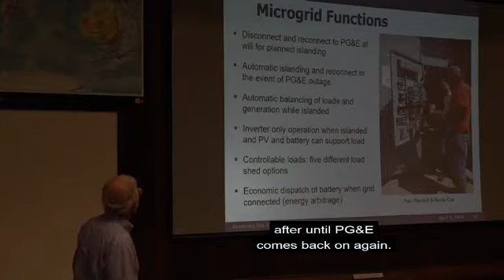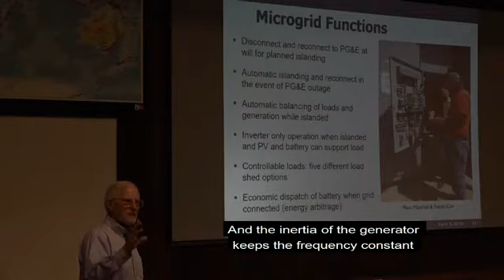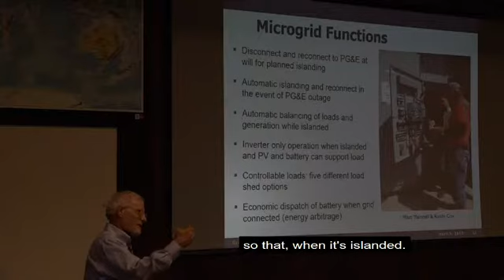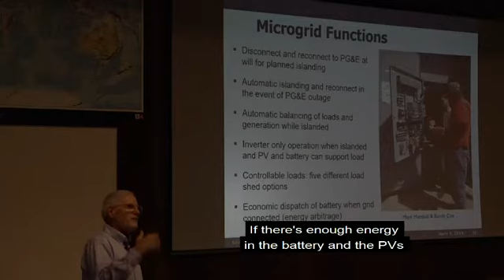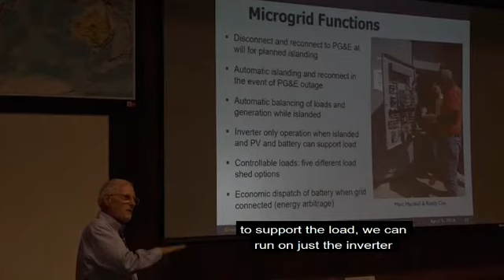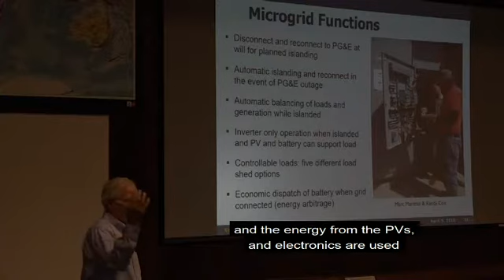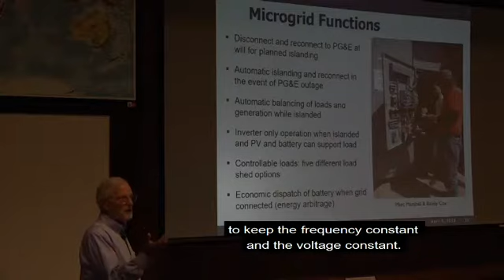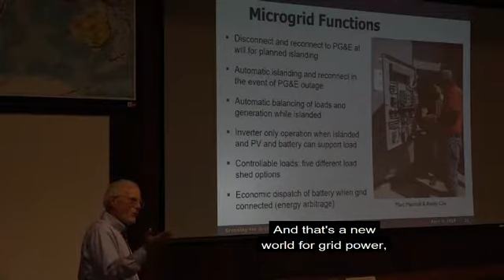The interesting thing is, most of our power systems rely on rotating generators, and the inertia of the generator keeps the frequency constant in the grid, which is very important. But this system can run on the inverter only, so when it's islanded, the generator is off. If there's enough energy in the battery and the PVs to support the load, we can run on just the inverter and the energy from the PVs, and electronics are used to keep the frequency and voltage constant. That's a new world for grid power, and this system does it well.